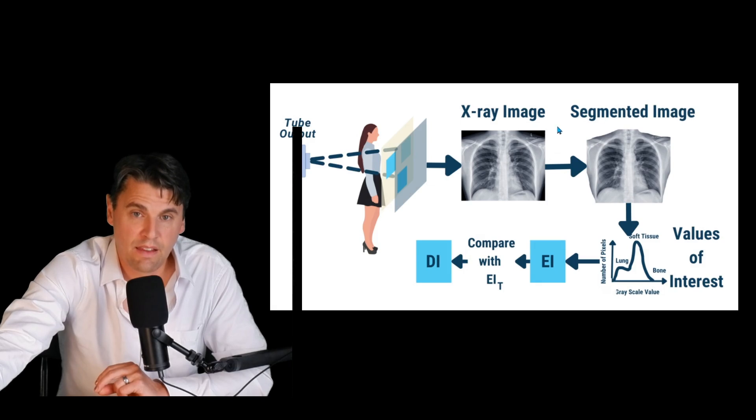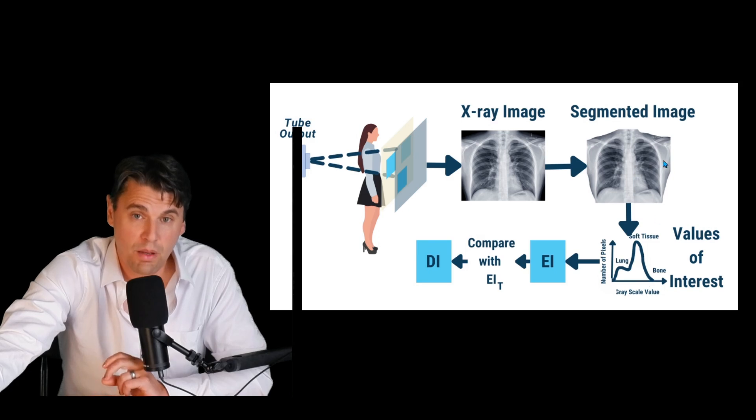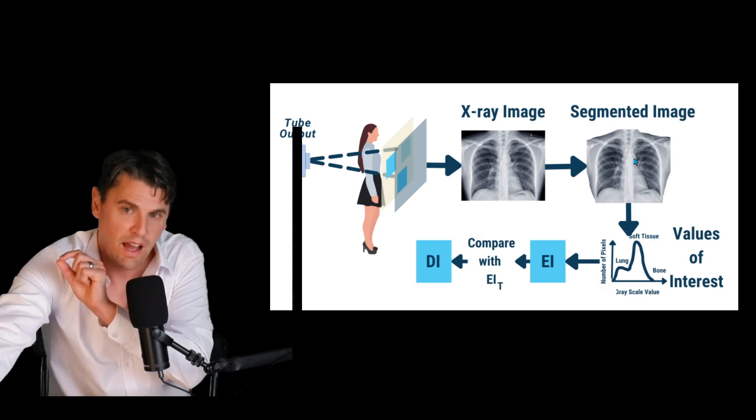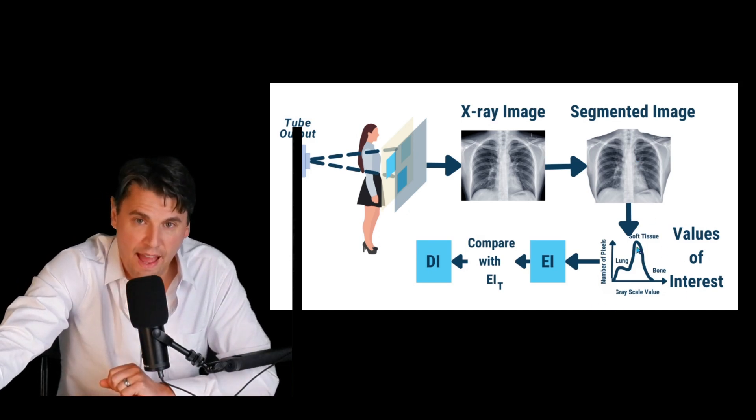We first identify what we call the values of interest. In that sense, we're actually just masking out all the dark pixels here that are outside of the actual patient. Once we get these values of interest, then we take what's called a histogram, where we're actually looking at each of the intensity values and counting how many times there was each of the different intensity values. Then we can use that along with calibrations of these numbers in order to get an exposure index.